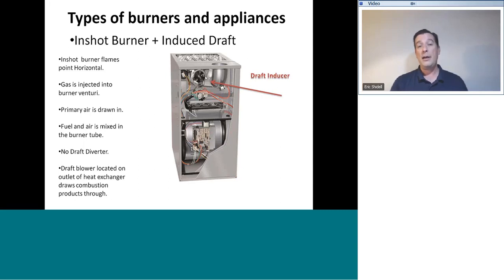If you are a stubborn mule, for example, and I hold out a carrot and I move the carrot along to get you to walk, I am inducing that animal to come towards me. The draft inducer does the same thing in that it encourages or pulls that draft through the furnace. It doesn't force it. It's not a blower. It is an inducer. It pulls.